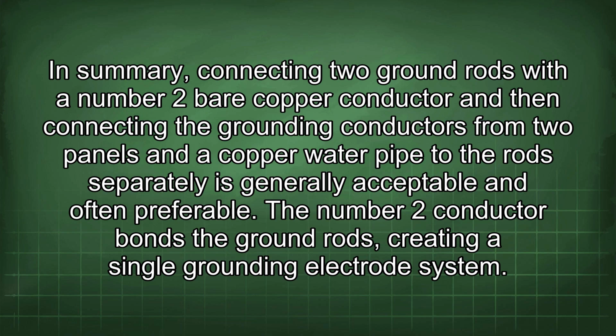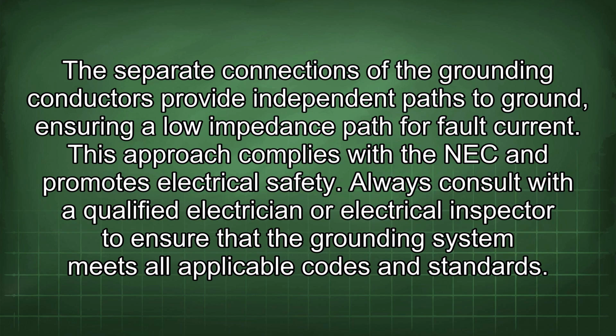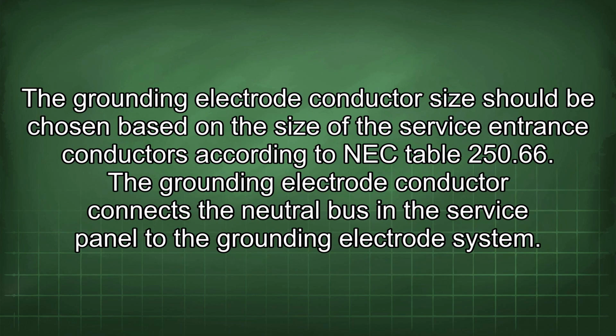The number 2 conductor bonds the ground rods, creating a single grounding electrode system. The separate connections of the grounding conductors provide independent paths to ground, ensuring a low impedance path for fault current. This approach complies with the NEC and promotes electrical safety. Always consult with a qualified electrician or electrical inspector to ensure that the grounding system meets all applicable codes and standards. The grounding electrode conductor size should be chosen based on the size of the service entrance conductors according to NEC Table 250.66. The grounding electrode conductor connects the neutral bus in the service panel to the grounding electrode system.